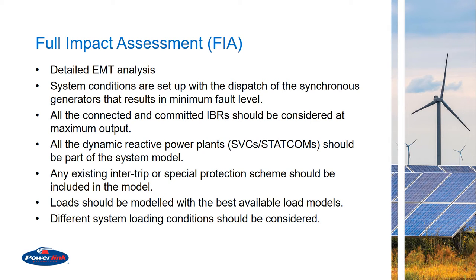When the connecting NSP undertakes a full impact assessment, certain detailed modeling is undertaken by the NSP. Some of the requirements for the modeling are that system conditions are set up with the dispatch of synchronous generators that result in the minimum fault level defined by AEMO. All the connected and committed inverter-based renewable or inverter-based plant should be considered in this analysis. All the dynamic reactive plants such as SVCs and STATCOMs must also be considered as part of this analysis.